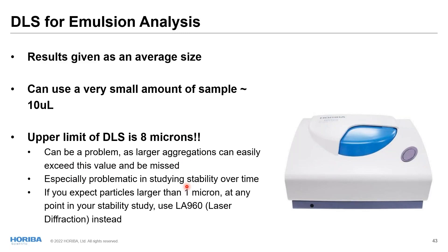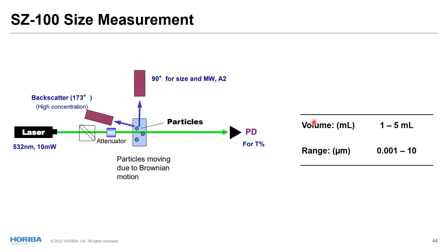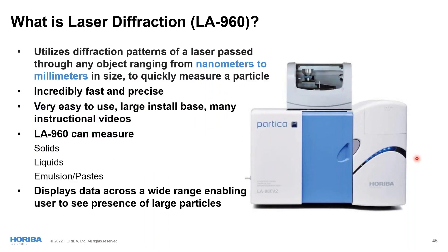For emulsion stability studies, you typically make samples, place them on a shelf, and watch them break apart over time, requiring particle size measurements that may grow beyond the micron barrier. If you expect particles larger than a micron, laser diffraction is more appropriate. The SZ100 measurement setup uses a laser through a cuvette, measuring at approximately 90 degrees with backscatter capability, using 1–5 mL sample volume with a measurement range from single-digit nanometers up to about 10 microns.